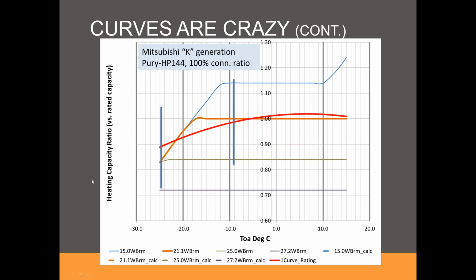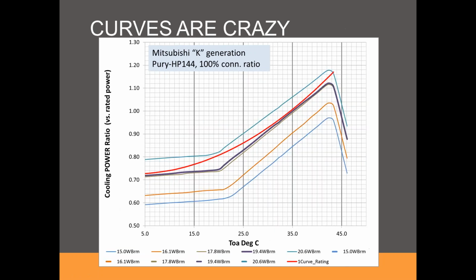This is another example, now for heating capacity. Once again, there's a pretty sharp inflection for what actually occurs for the capacity of the heating mode of the equipment. And if you apply a single curve, it doesn't reflect what's actually going on. And so the key aspect of EnergyPlus is that it allows you to make one segment for low, one segment for high, and you define the boundary condition so that you reflect the actual performance in capacity or power correctly.